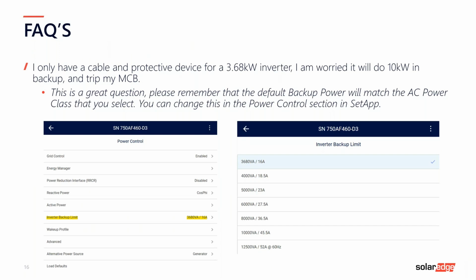Last question: if the inverter is set to 3.68 to match the generation, and the customer decides to add more PV at a later date, can the inverter be reset to match the new generation with DNO approval? Absolutely, yes, it can. We can go up to 10 kilowatts, so rather than installing another inverter, you would simply upgrade the AC supply to the inverter and change it to up to 10 kilowatts.